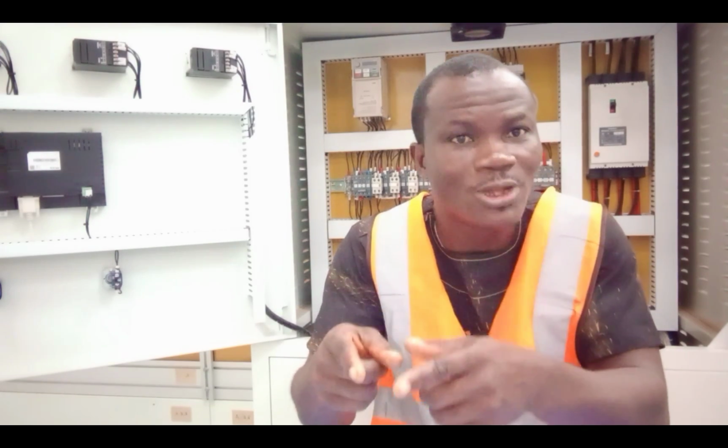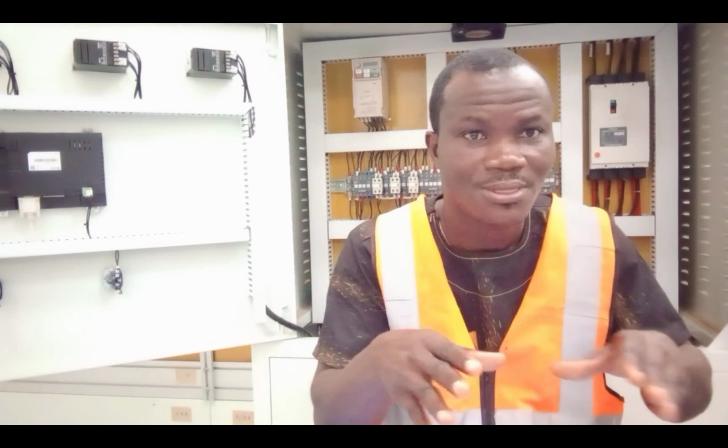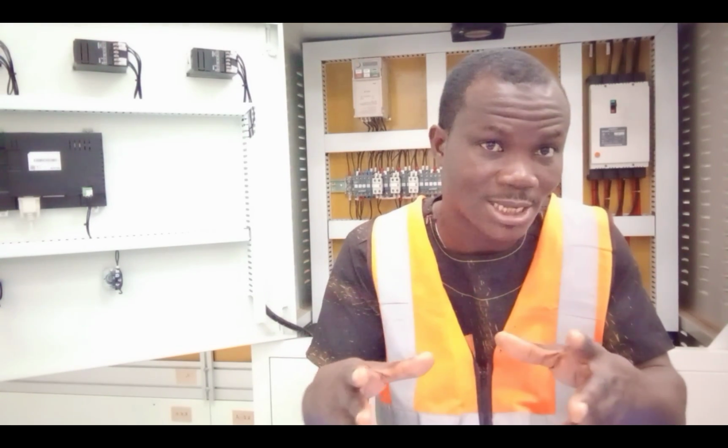And because the RCCB is in the circuit, the moment that current flows through your body, the RCD will operate to switch the supply off. Because when that current that is supposed to pass through you and give you the electric shock is flowing through you, the amount of current flowing through the live conductor at that particular moment will be more than the current returning through the neutral wire. That creates an imbalance in the circuit, and the RCCB will operate, and that saves you from receiving the electric shock. When we talk of leakage, leakage means that a part of the current flowing in the live conductor is now leaking and flowing into other metal.